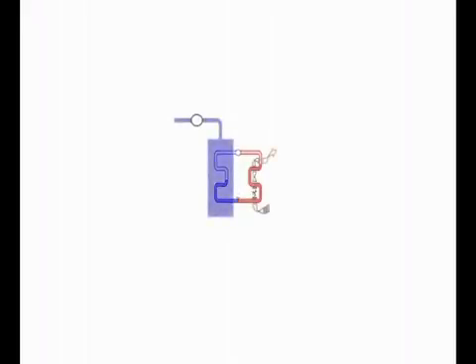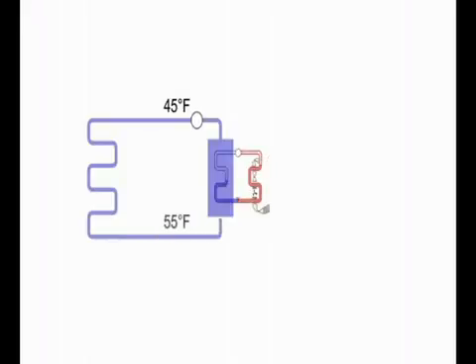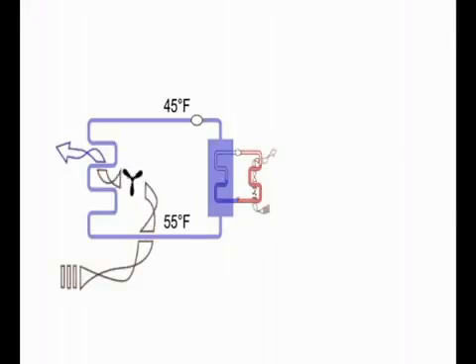Air performs reasonably at carrying cold air, but water is better at heat exchange and does a superior job keeping cold over long distances. For this reason, many buildings, and some campuses or city districts, utilize chilled water. In this regime, pumps carry water chilled on the evaporator side, which is to say the cold side, of the compression refrigeration loop, to sometimes distant air handling units. The air handling unit then blows air across coils of chilled water rather than coils of chilled coolant as we saw in previous examples, thereby cooling 70-degree return air to 50 degrees for distribution through ducts.